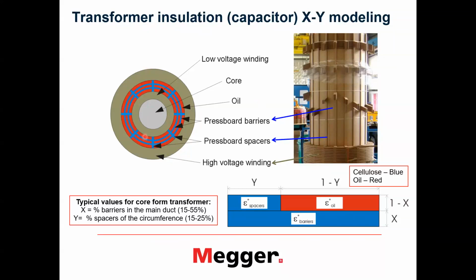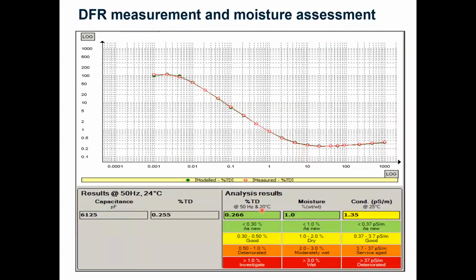And this is the model of a transformer winding, where we have the core, we have low voltage windings, then we have spacers and barriers and oil gaps, and then we have a high voltage winding around it. And it is maybe not that detailed as shown here, but we can see the barriers and spacers hanging here, which is then reduced to a big barrier, a big spacer, and a big gap of oil in order to make easier calculations of the resulting model. And this is something that we have in the IDAX software, which is basically our method for moisture assessment in transformers.